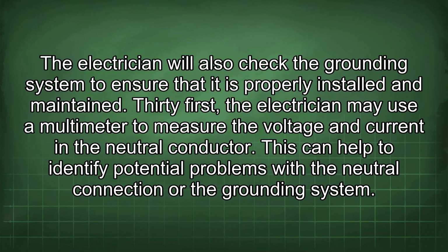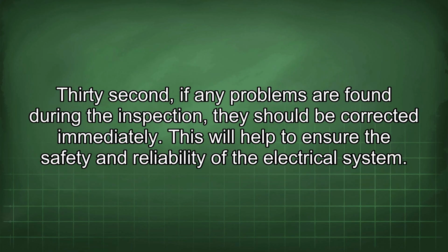31st, the electrician may use a multimeter to measure the voltage and current in the neutral conductor. This can help to identify potential problems with the neutral connection or the grounding system. 32nd, if any problems are found during the inspection, they should be corrected immediately. This will help to ensure the safety and reliability of the electrical system.